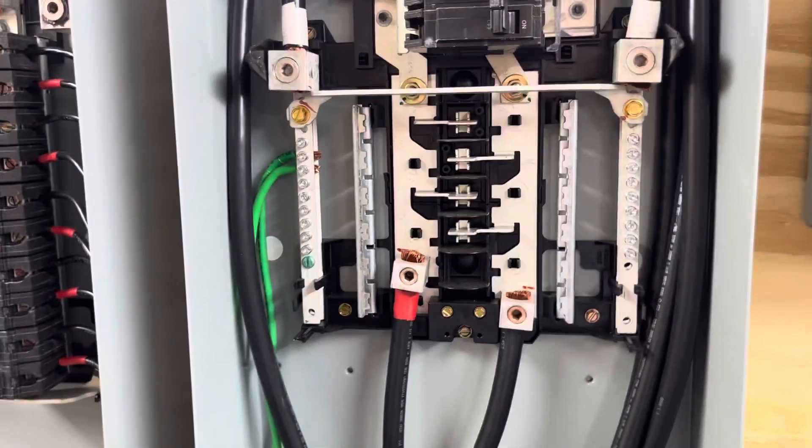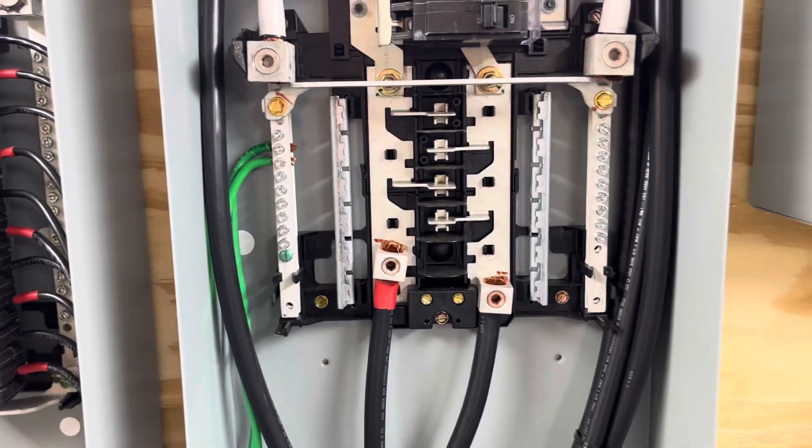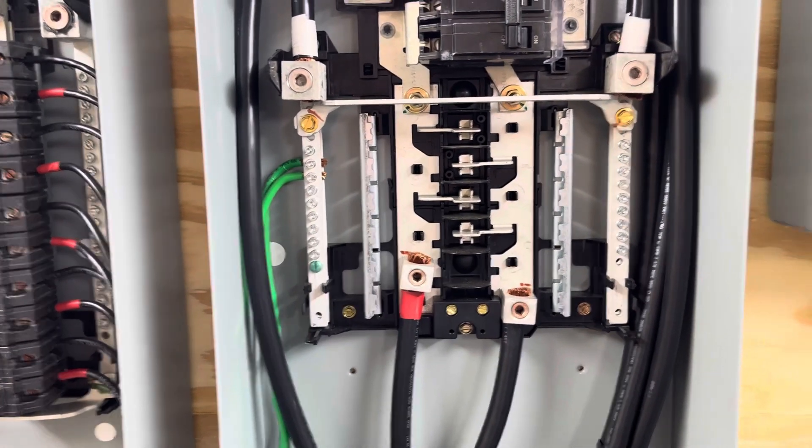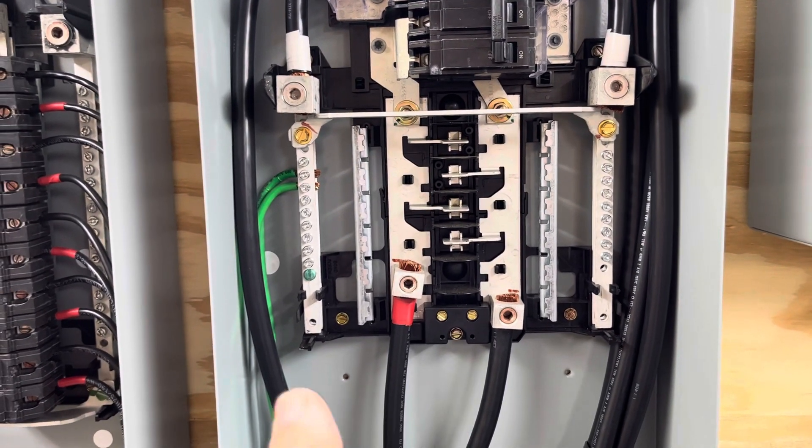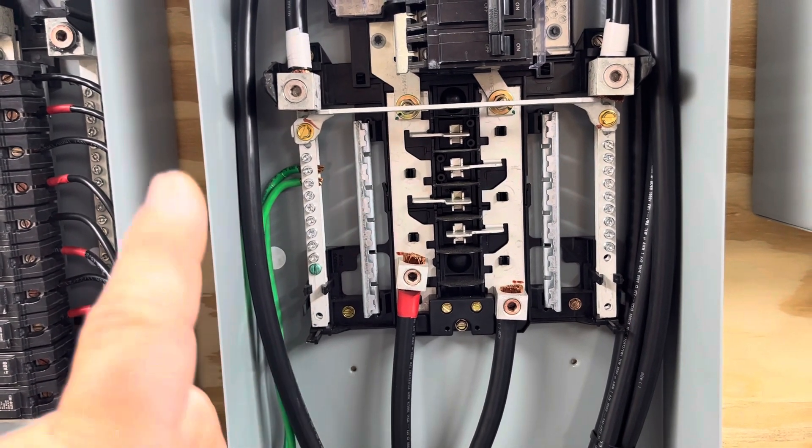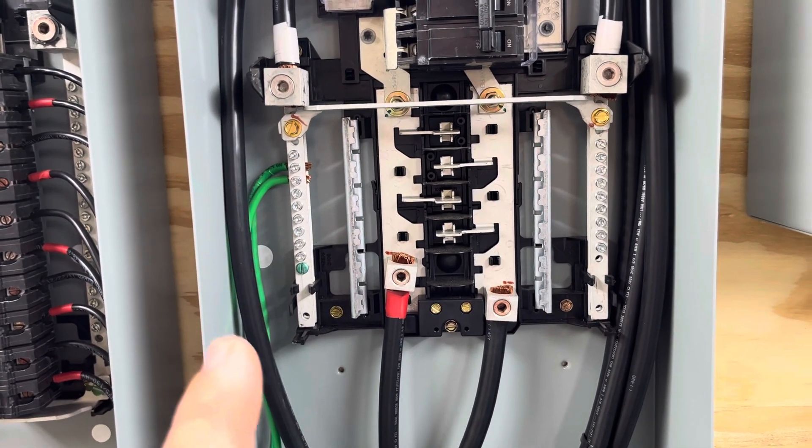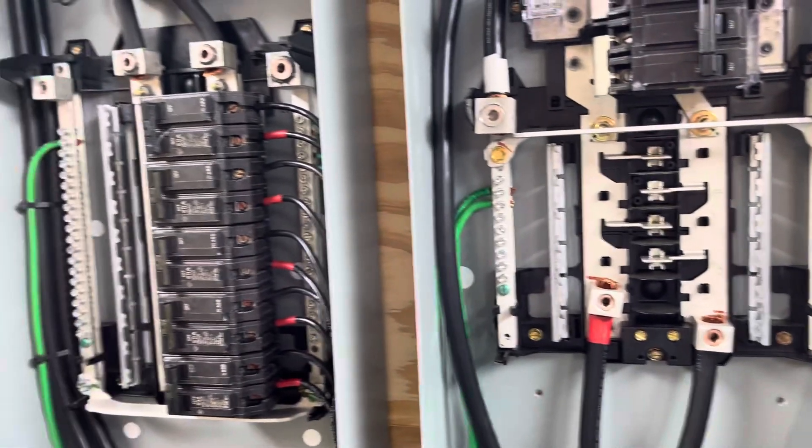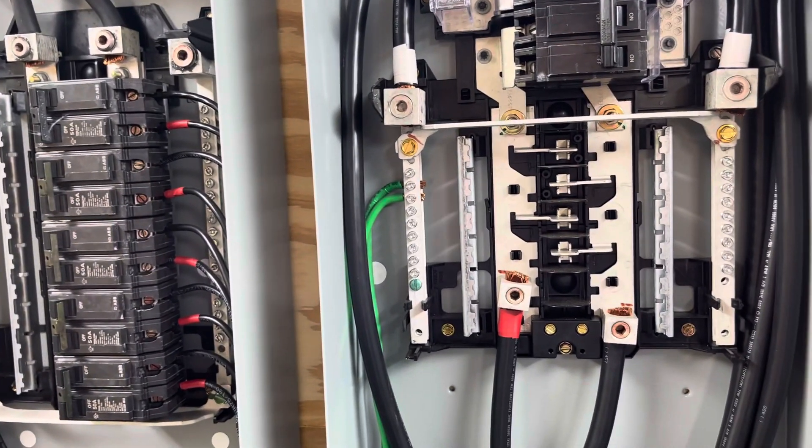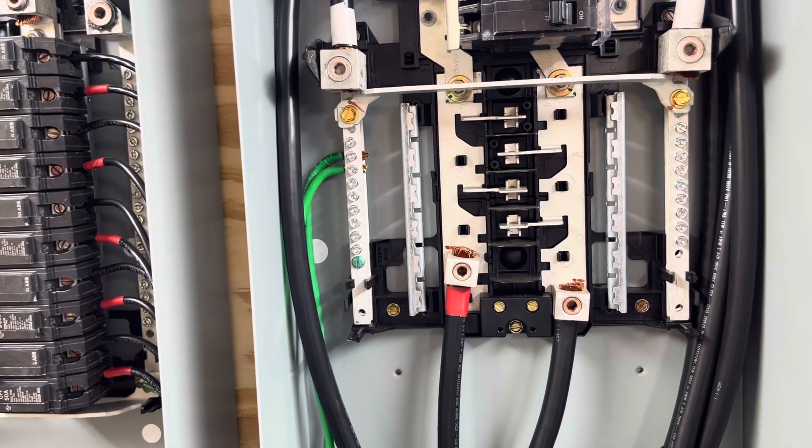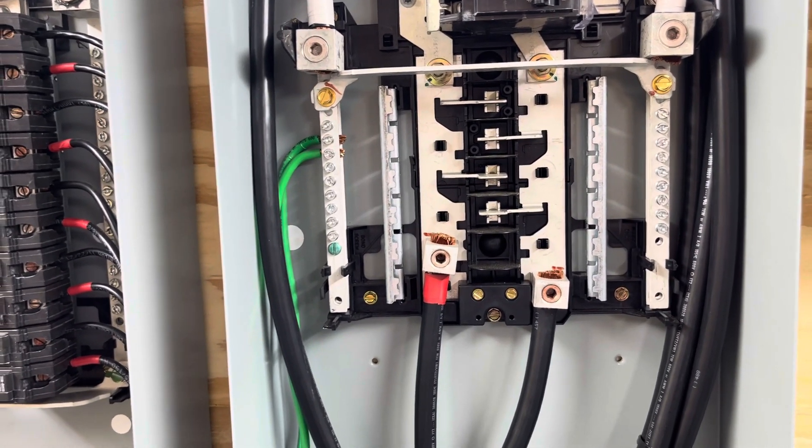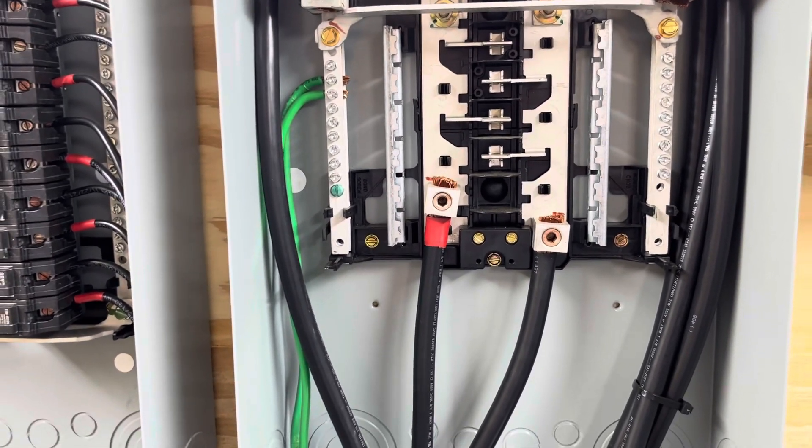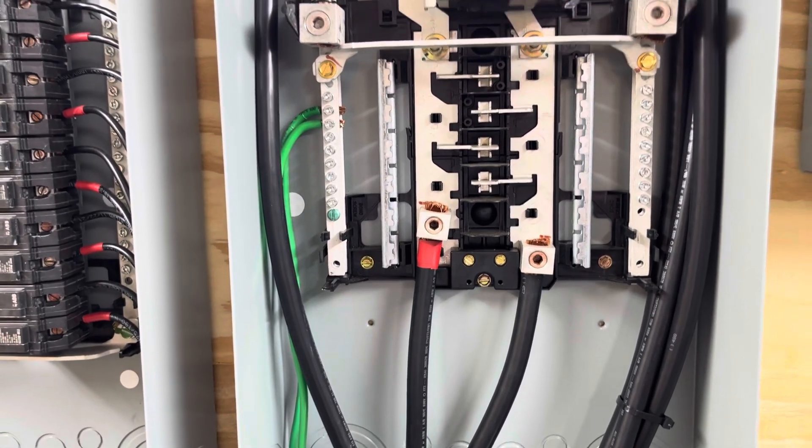Now I've showed you the voltages before in a previous video of how the voltages remain consistent phase to ground or line to ground, L1 to ground, L2 to ground, regardless of whether the inverter is in bypass or inverter mode. There will be no ground loops because of the isolation transformer.